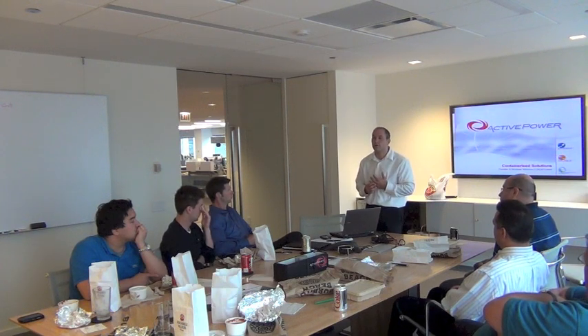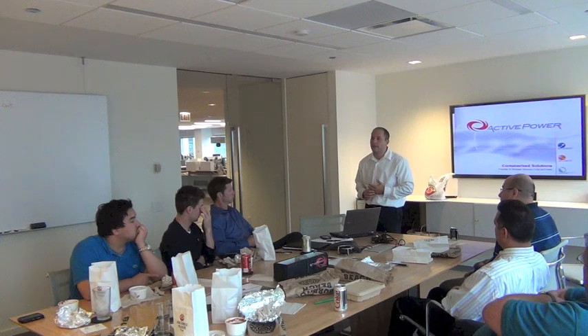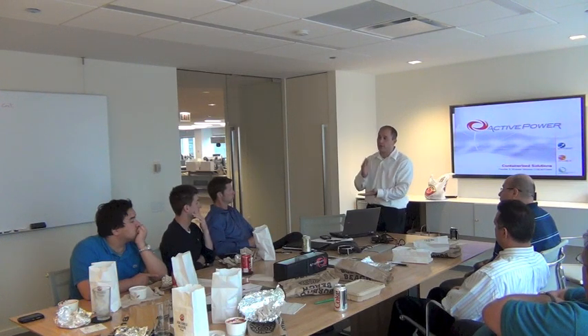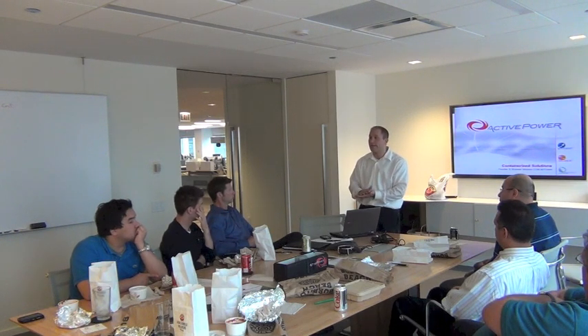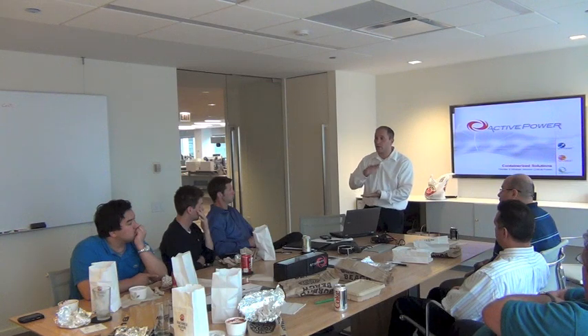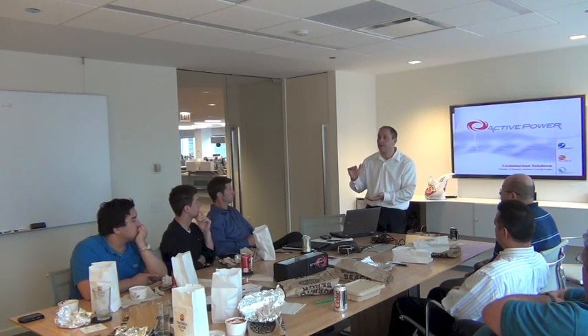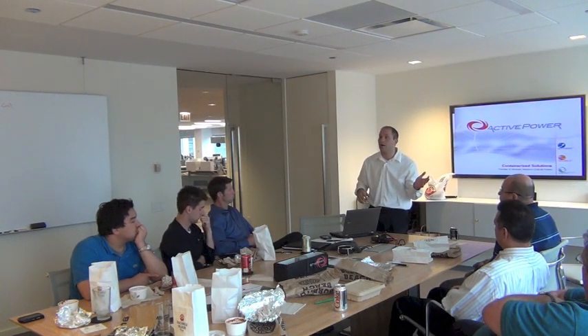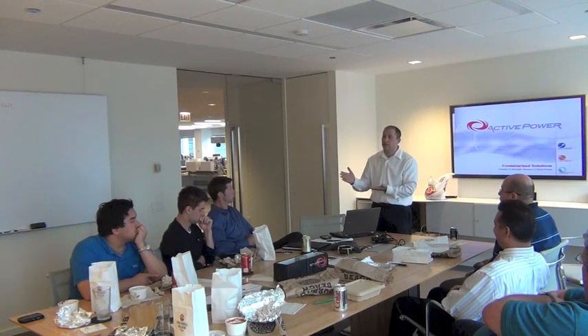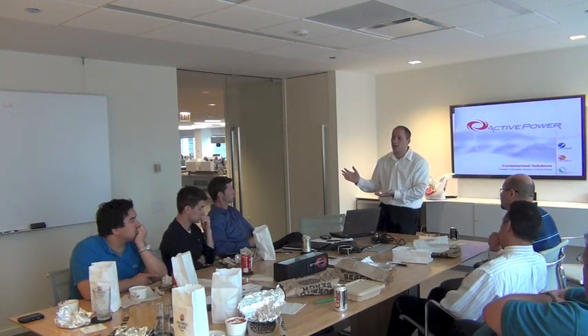The nice thing with our techs and our integrated packages is we're really designing around flywheels. So when your generator comes up to speed in 9-10 seconds, by the time you reach 12 seconds of flywheel energy, it's a very good chance that all the load is already walked onto the generator. So when we specify 14.5 seconds at 100% load, we expect to make it on. We expect to have all the load on generator well before we're out of flywheel energy.